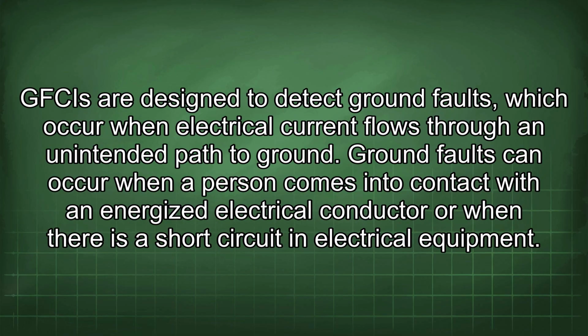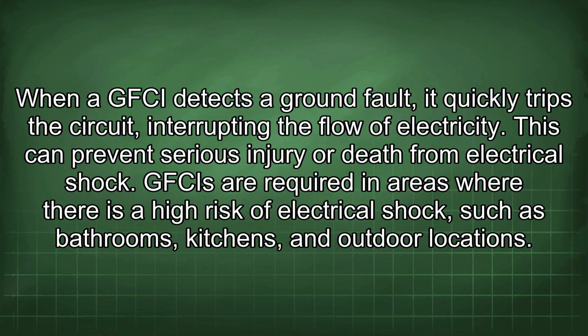GFCIs are designed to detect ground faults, which occur when electrical current flows through an unintended path to ground. Ground faults can occur when a person comes into contact with an energized electrical conductor or when there is a short circuit in electrical equipment. When a GFCI detects a ground fault, it quickly trips the circuit, interrupting the flow of electricity. This can prevent serious injury or death from electrical shock.